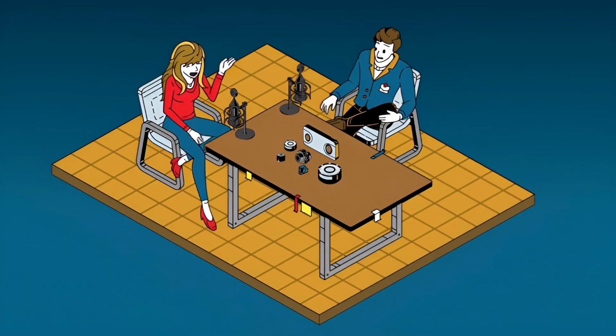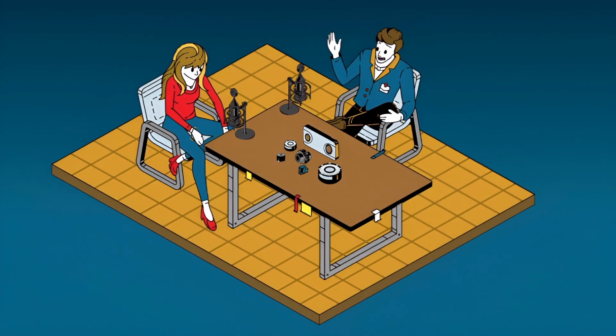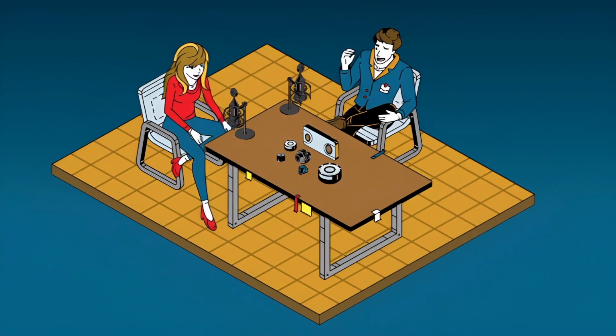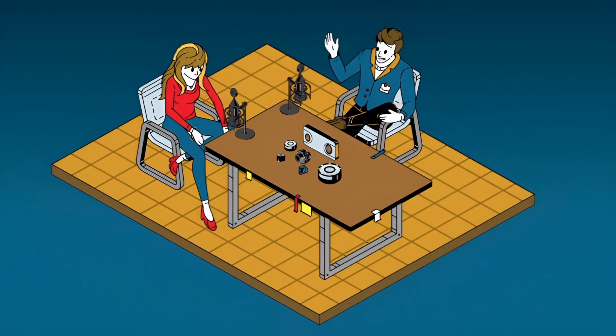Precisely. The second killer is related, but it's caused by quick, blunt events. Mechanical damage. Physical trauma. Yes. This isn't necessarily too much force in the application itself. It's like dropping the sensor or a sharp impact during installation. Exactly. Think about the components inside. They are extraordinarily fine-tuned. A hard drop or even just constant excessive vibration can shift those delicate internal components, or it can damage the bond between the strain gauges and the sensing elements. So the outside might look fine. The housing might look perfect, but the internal alignment is shot, and that immediately throws the sensor out of calibration.